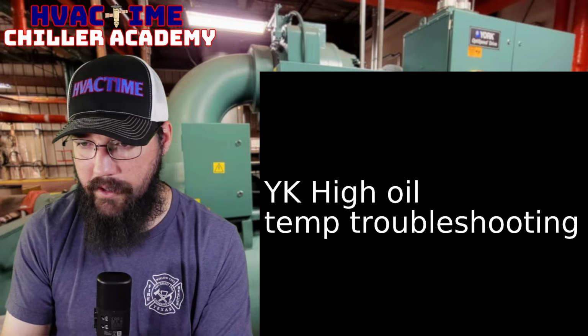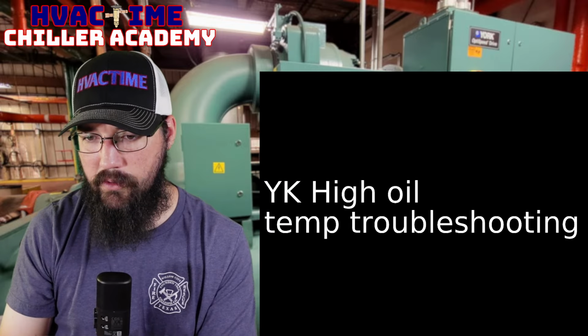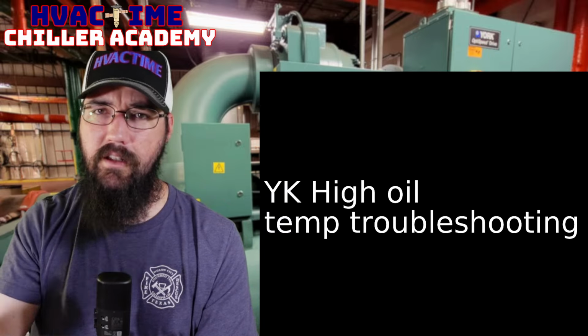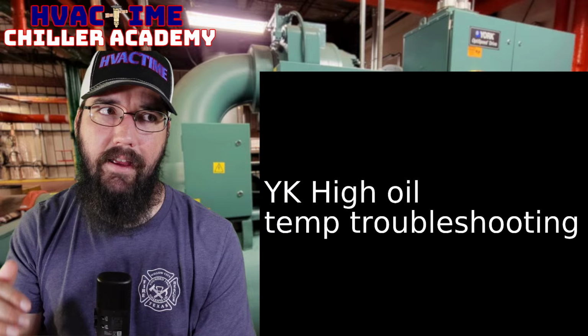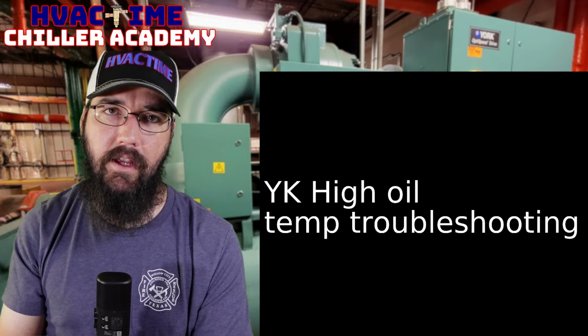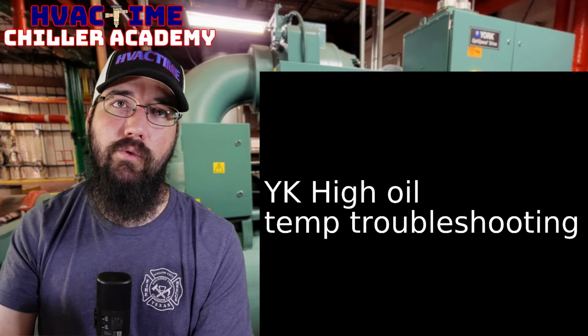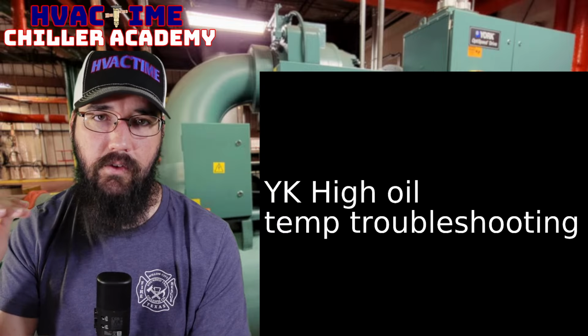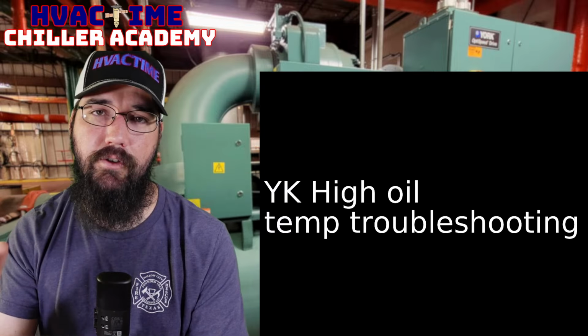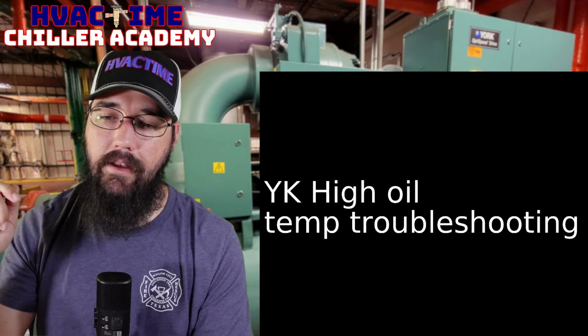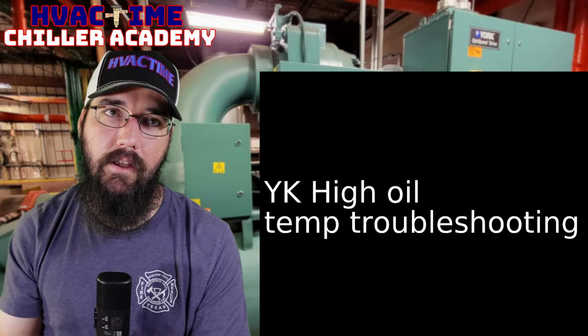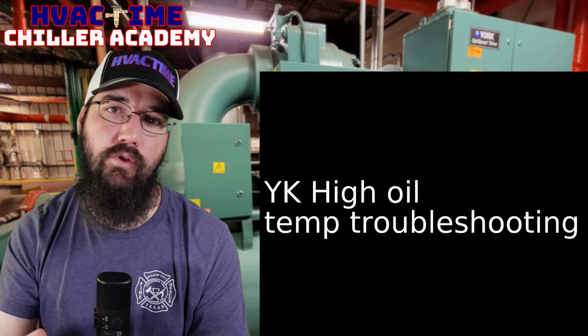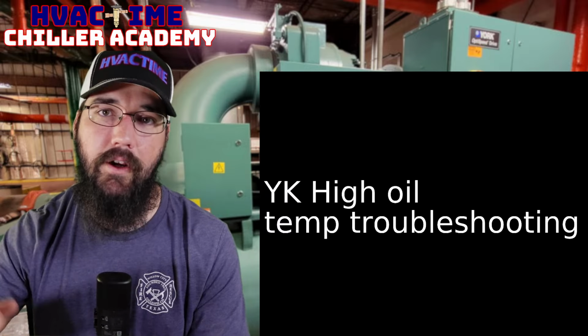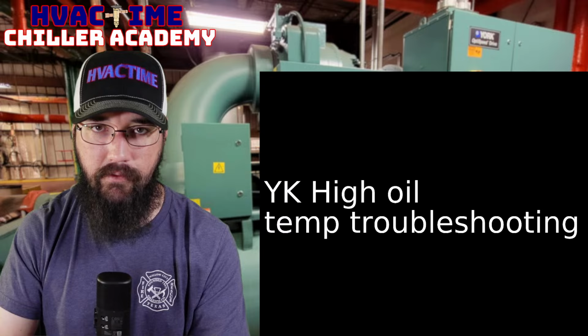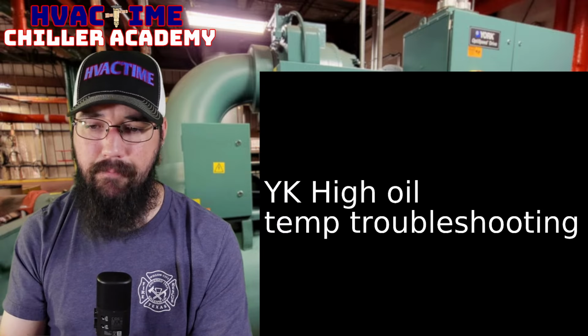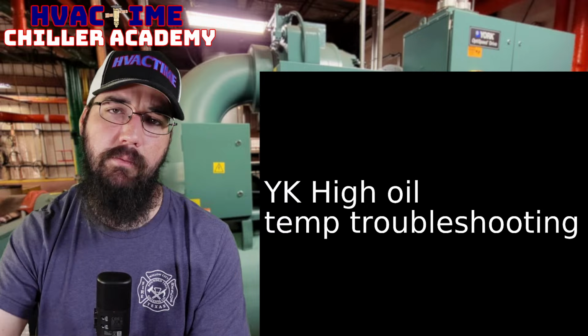All right, so you weren't there, but what is a typical subcooling value to look for? Fully loaded and everything set correctly, like your liquid level on the condenser, you should be able to run 8 to 12 degrees of subcooling. That's the subcooling target we should be trying to hit. When the machine is unloaded, it's common to see that get down into say 4 to 8 degrees, and float in that range. That's very normal when derated at an unloaded state. And then as the machine loads up, you should see that subcooling increase.